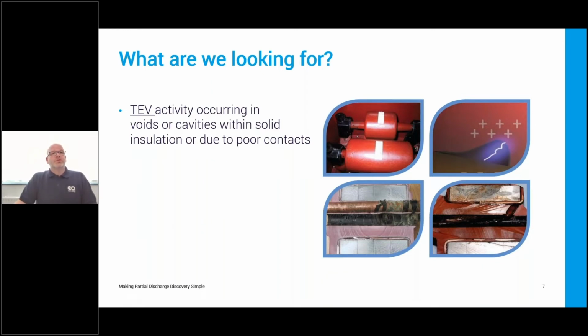So just to summarize the what is PD section of the webinar, when we're looking for TEV, we're looking for internal PD activity within the insulation. On these pictures here, for example, of a CT, you can see where voids have developed in the insulation layer and PD activity has increased.